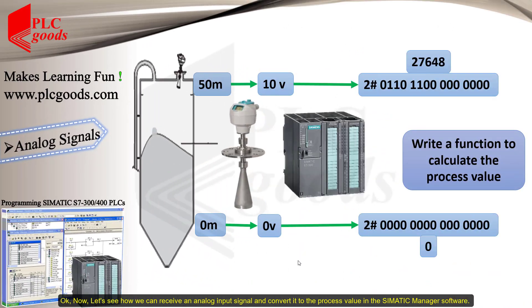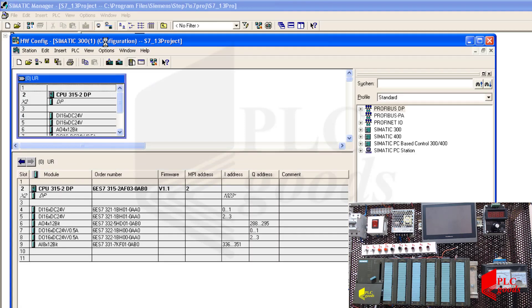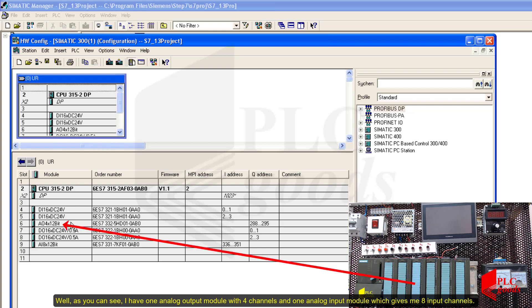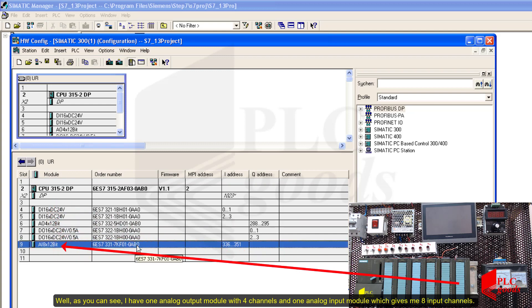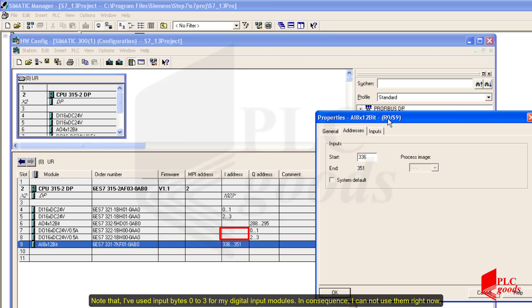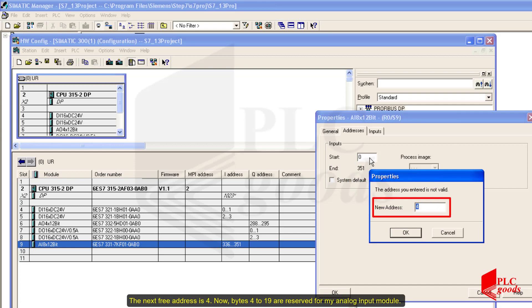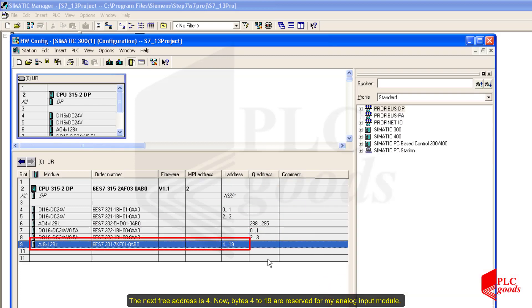Now let's see how we can receive an analog input signal and convert it to the process value in the Simatic Manager software. I configured my PLC station in the previous videos. As you can see, I have one analog output module with four channels and one analog input module which gives me eight input channels. Let me change the default addresses of the analog input module — I've used input bytes 0 to 3 for my digital input modules, so the next free address is 4. Bytes 4 to 19 are now reserved for my analog input module.